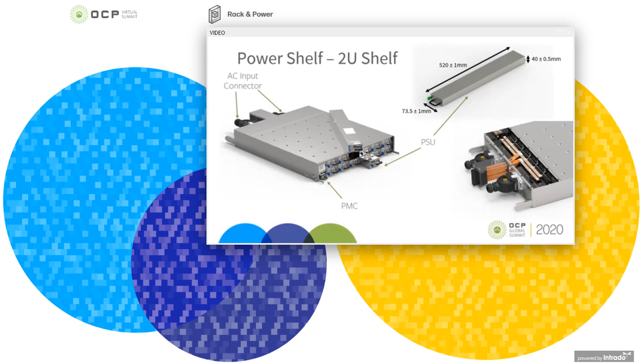In the rear of the system, there are two large input connectors used for the AC in, which can accommodate higher power up to 60 amps. The shelf is also recessed a bit more in the rear to accommodate this AC input connector size and cable bend radius. The DC output connector, which clips onto the bus bar, is also identical between the 1U and 2U shelves. The only difference is that there are two such clips on the 2U instead of just one.